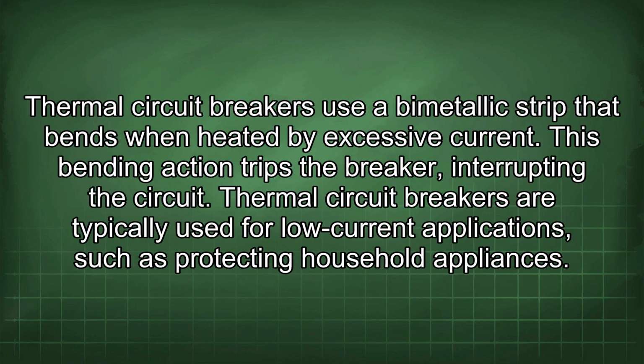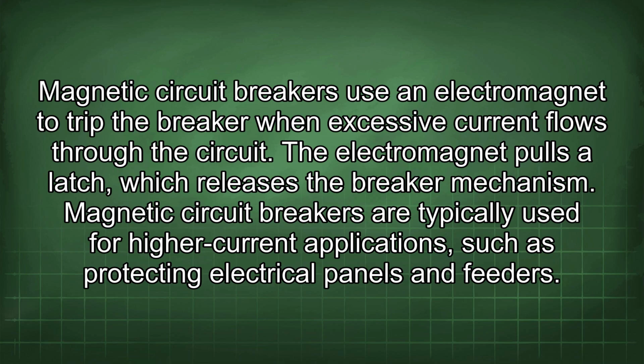Thermal circuit breakers use a bimetallic strip that bends when heated by excessive current. This bending action trips the breaker, interrupting the circuit. Thermal circuit breakers are typically used for low current applications, such as protecting household appliances. Magnetic circuit breakers use an electromagnet to trip the breaker when excessive current flows through the circuit. The electromagnet pulls a latch, which releases the breaker mechanism. Magnetic circuit breakers are typically used for higher current applications, such as protecting electrical panels and feeders.